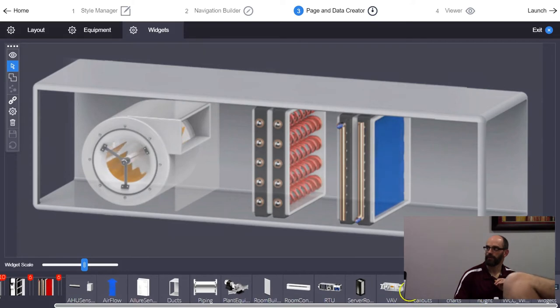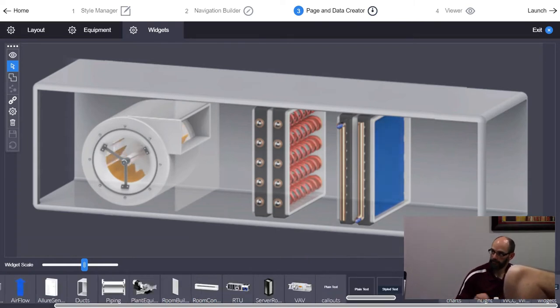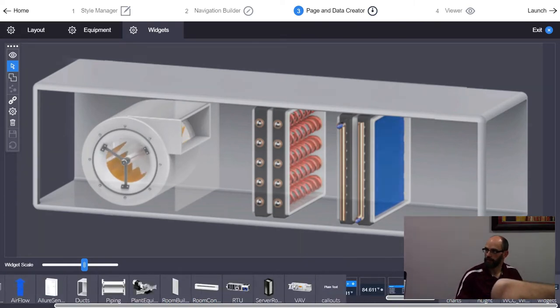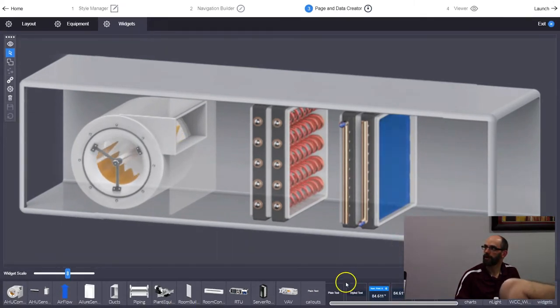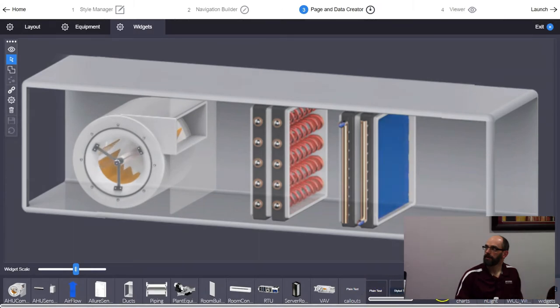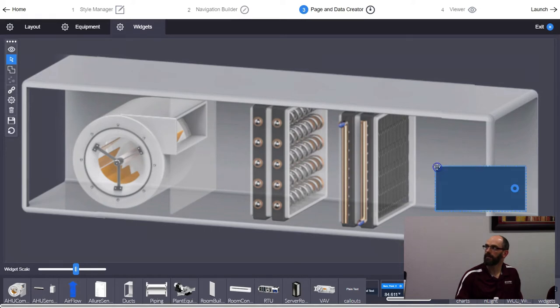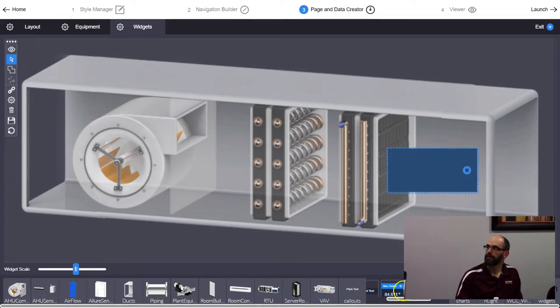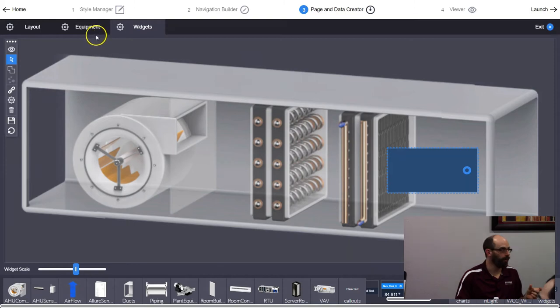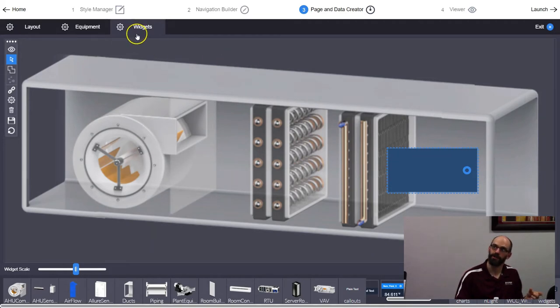Now go to the Widgets layer — this is where we put all the other cool stuff on the graphic. We'll start with call-outs. Call-outs are by far the most confusing part. I'm going to pull in a Node Value call-out and make this my supply temperature point. Make sure you're on the Widgets tab when doing this — if you're on the wrong layer and paste a widget, it won't work. It does all kinds of weird stuff when a widget is on the wrong layer.